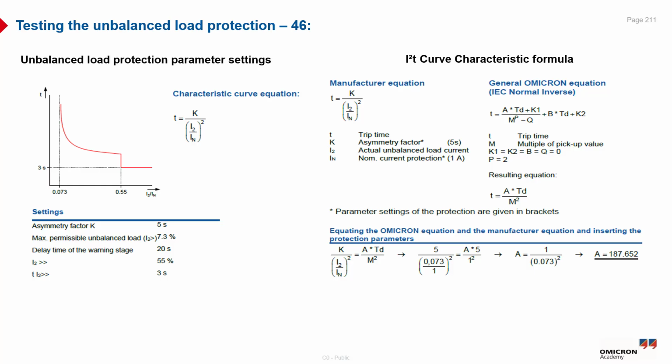When using the overcurrent test module, the test object definitions have to be configured accordingly. For better distinction of the various overcurrent relay functions in the test object, you can rename the new function to unbalanced load. The settings are performed in the negative sequence fault group, and all other fault groups are deactivated. The unbalanced load tripping characteristic is manufacturer specific and has to be added as a new standard characteristic for testing. The table shows the definition of this characteristic curve in the Test Universe software.